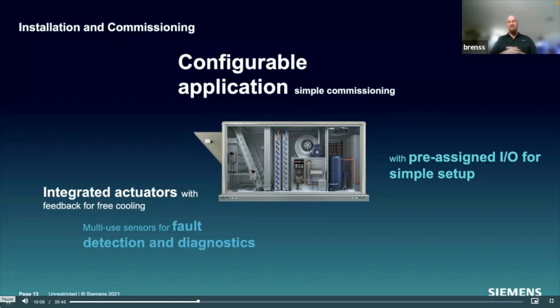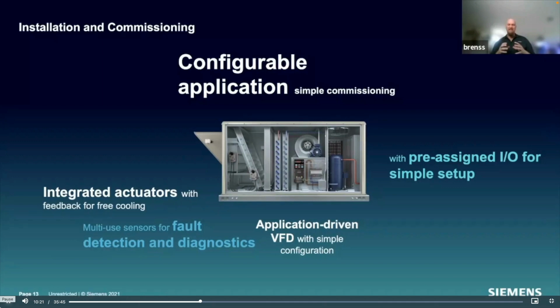Pre-assigned IOs, simple wiring per the wiring diagram. If you just wire up for that, it'll be as simple as can be. And it's over and over. If all the units are cosmetically the same, it goes as simple as can be. It's all an application-driven solution. The VFD is built into the controller. We all know that there's 5,000 parameters inside of a VFD. Literally now there's just one.